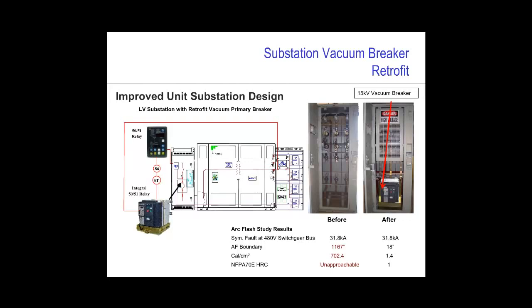Because this facility operates in a process environment, it was quite frequent that the feeder breakers on the low voltage switchgear would be racked out as a part of the lockout tagout procedure while the rest of the substation remained energized. Because the substation was existing, the facility was actually landlocked. There was no physical way to add a secondary main breaker.